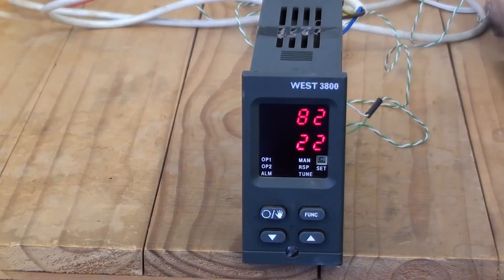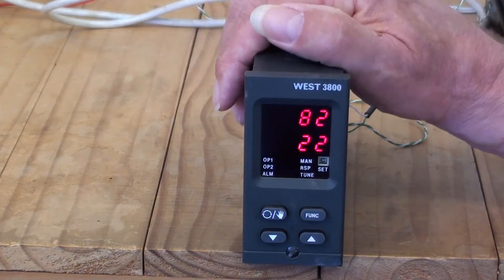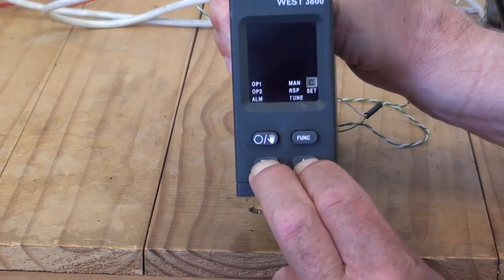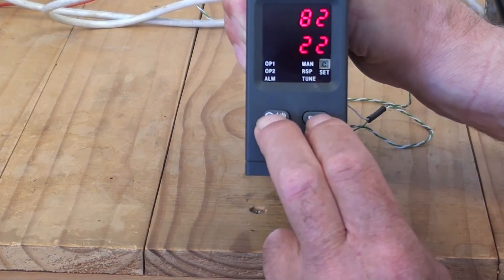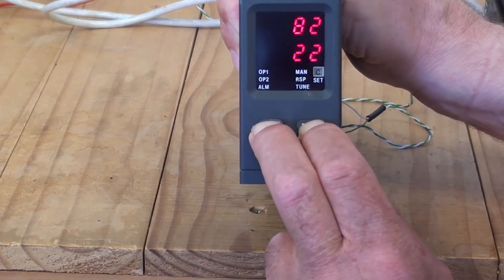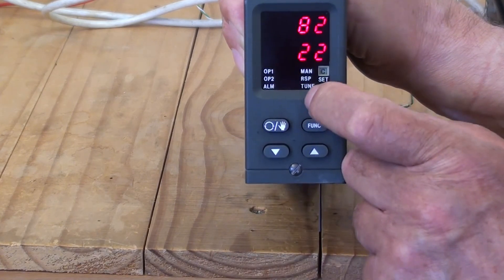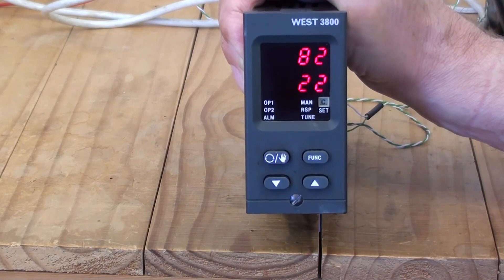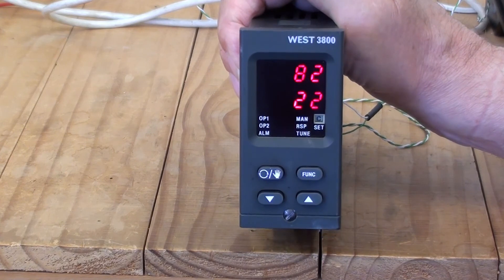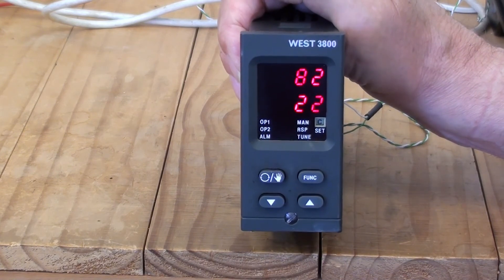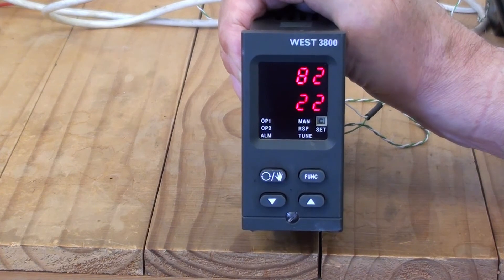The controller has a pre-tune and self-tune feature. To enter the pre-tune and self-tune, press the up and down arrows together and hold for about five seconds until the set light flashes. Now press the auto manual and the function key together. The set light goes off and the tuning light goes on. The controller is now going through the pre-tune feature and once it's finished it will then go to self-tune.